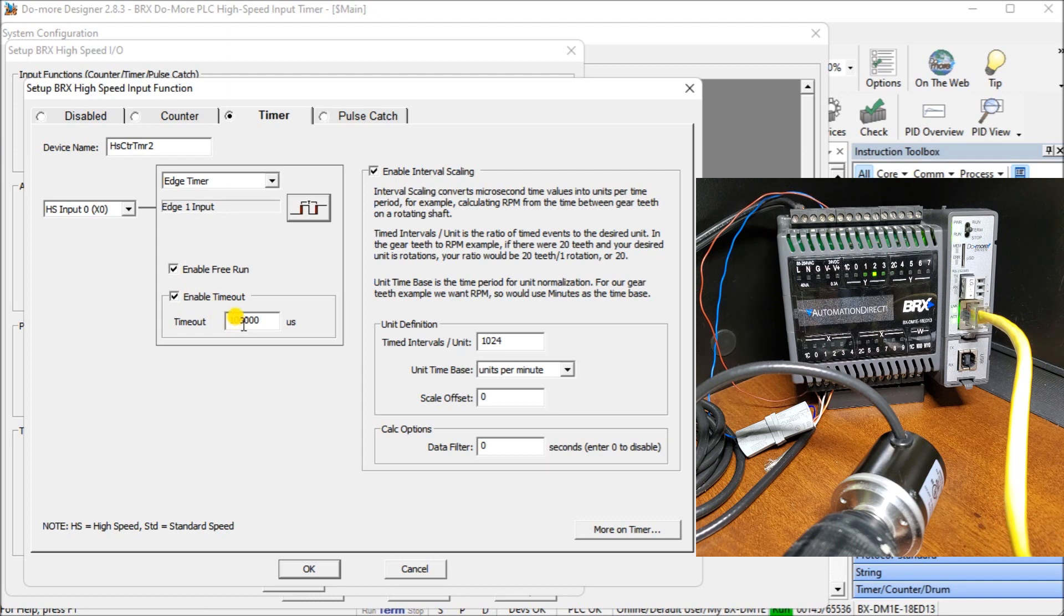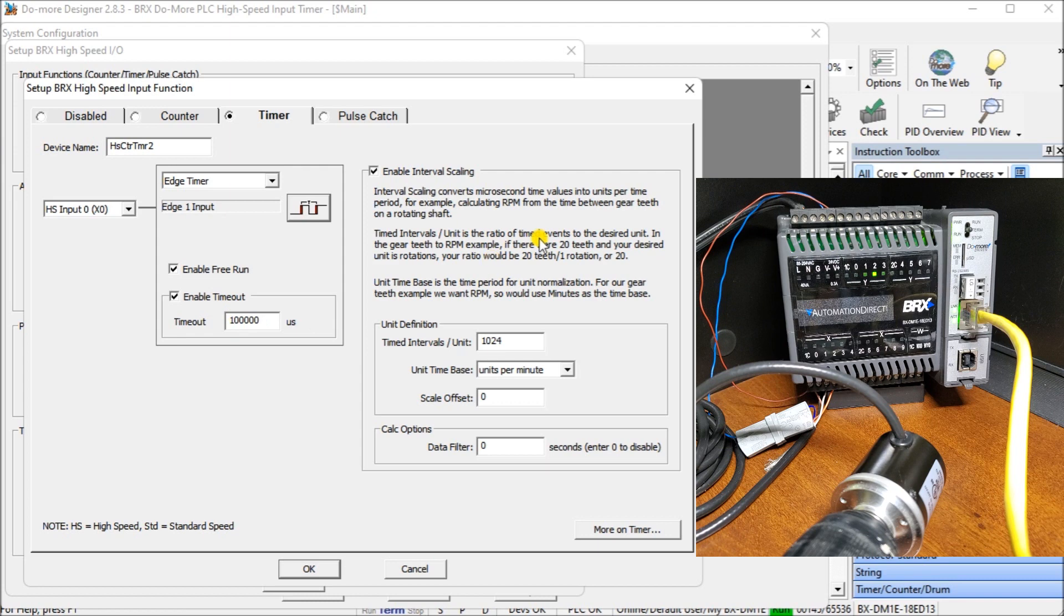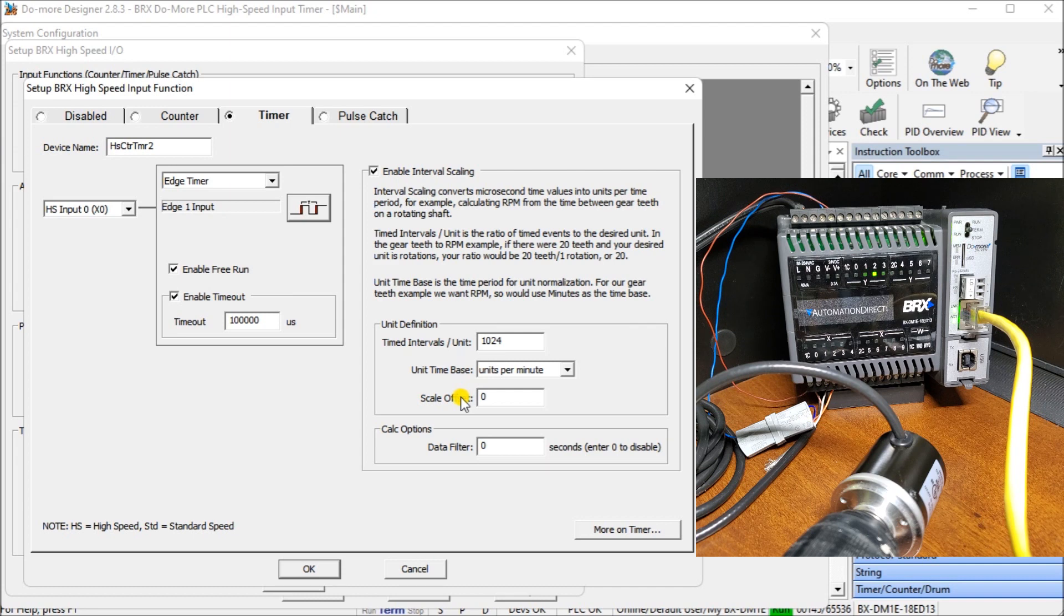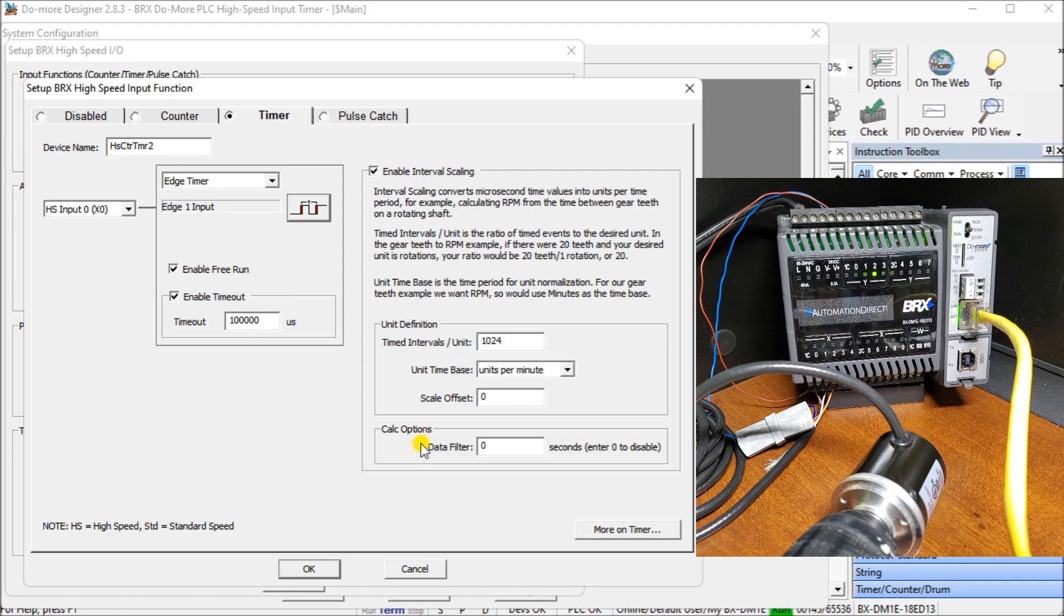Then we're going to enable our scaling value, and our timed units will be 1024, which is the pulses per rev on our incremental encoder. Then we'll have our unit base time of minutes, so we're going to have revolutions per minute. Our scale offset, this will be an offset value that we can add. Right now, we're going to leave it at zero, so we would just want the RPM directly. Then we have calculated options that can calculate over time what that value is going to be, the average over time. So we can put so many seconds if we wanted to do it that way. That way it'll slow down that output being updated.